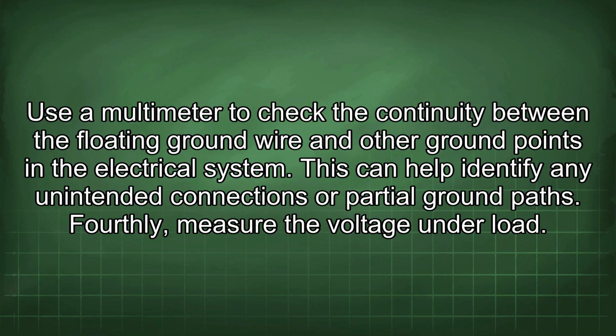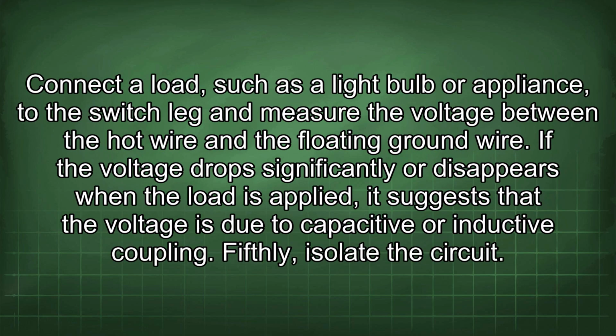Fourthly, measure the voltage under load. Connect a load, such as a light bulb or appliance, to the switch leg and measure the voltage between the hot wire and the floating ground wire. If the voltage drops significantly or disappears when the load is applied, it suggests that the voltage is due to capacitive or inductive coupling.